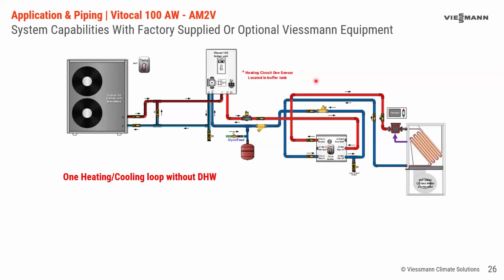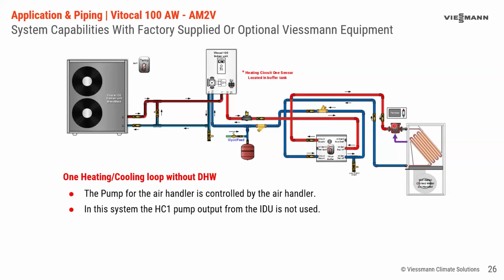So once we put it together, and again, we'll go back and look at without DHW, we looked that up to the buffer tank, but let's look beyond the buffer tank. In this application, we see an air handler. Now this is maybe heating only, maybe it's chilled water only, maybe it's a hot water, chilled water air handler. It doesn't matter. And you're going to set the function of hot water or chilled water based on how you have the control set or the jumpers that are in there, right? But the heat pump is going to move energy through the indoor unit to the buffer tank, and then the air handler is going to draw off the buffer tank. But because this air handler has its own pump output, we're not going to use the pump output for the heat circuit or cooling circuit 1. It's going to be active inside the unit, but we don't have anything connected to it. We're going to use the air handler's pump, which will be triggered on by the thermostat calling for cooling or heating, and then our buffer tank is going to pull the energy.